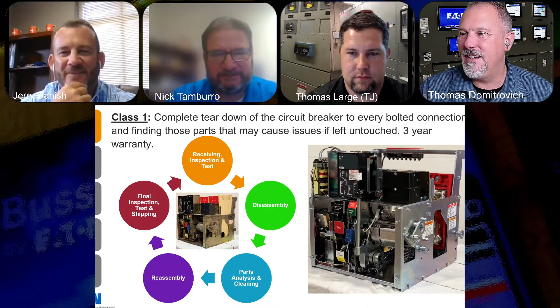So anything else on reconditioning? Yesterday, Jerry, we talked about taking a piece of equipment, putting cartridges in, basically putting a new breaker into that assembly. This is, you've got your assembly. I'm going to take the existing breaker out, recondition it, and put it right back into the same slot, right? Right. So you can do a 1-for-1.